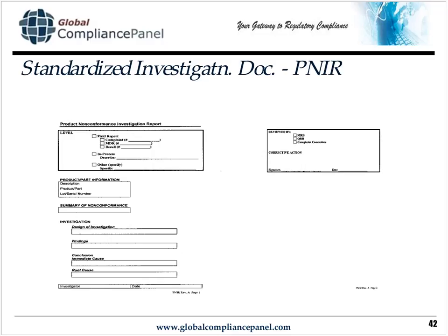And then after the conclusion is completed and the investigator signs their name, one of your interdepartmental bodies should review this record of investigation. It's either going to be your material review board, if it's an incoming component, a quality review board, which this company has and which meets quarterly to look at quality nonconformances, or a complaint committee, which usually meets monthly to look at complaints. And it's not the investigator that determines corrective action. It should be an interdepartmental body.